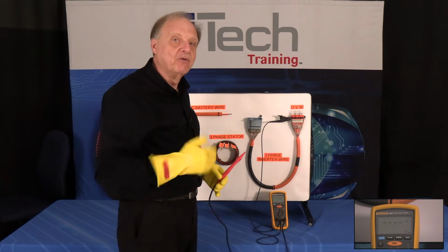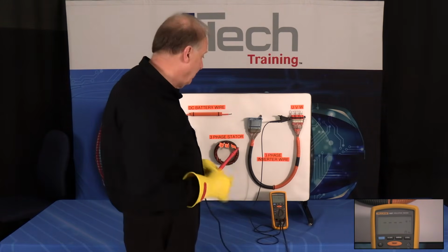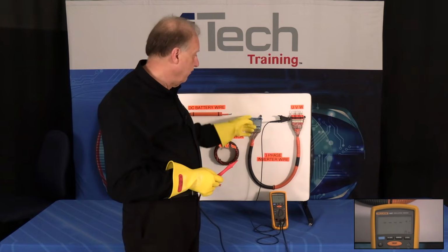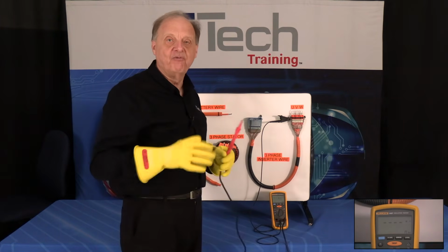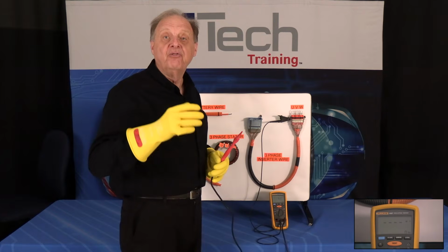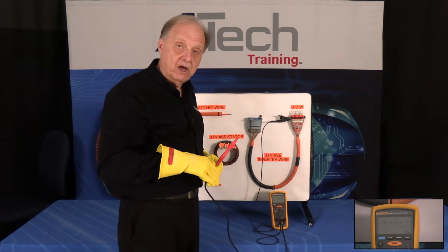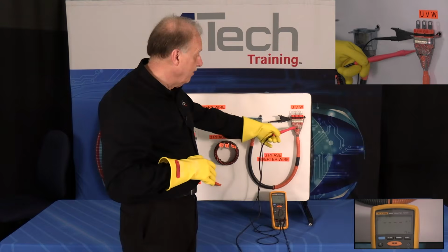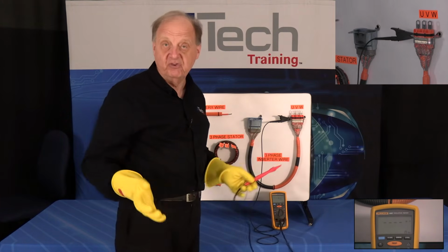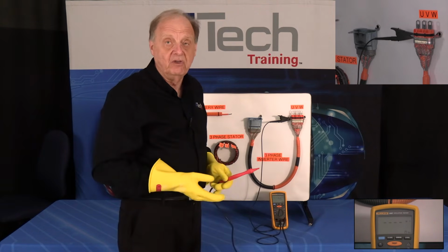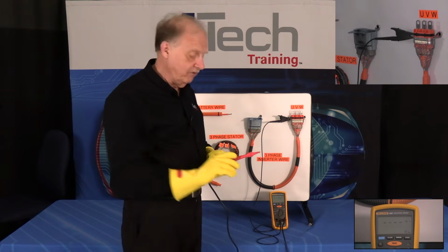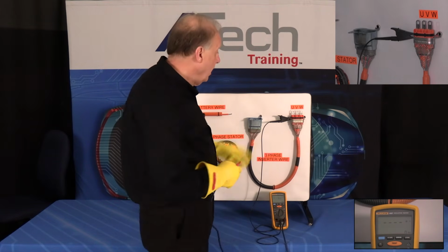We're going to look at the 3-phase inverter wiring up here. The big thing about it is there are three different things you need to look at. The system can be shorted - if you look at the grid, we've got a nice little mesh here, that's your shield. It can be shorted to the shield, or it can be shorted internally to each one. So the first thing we want to do is go out and check.